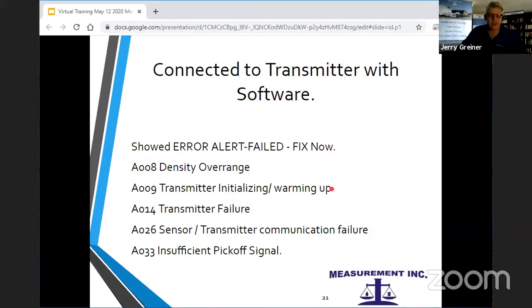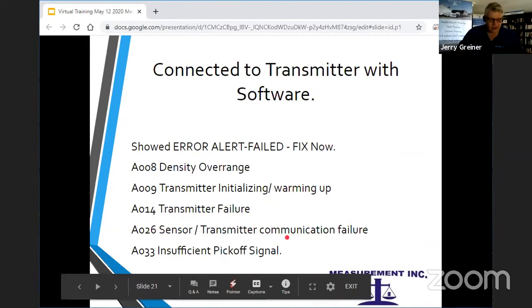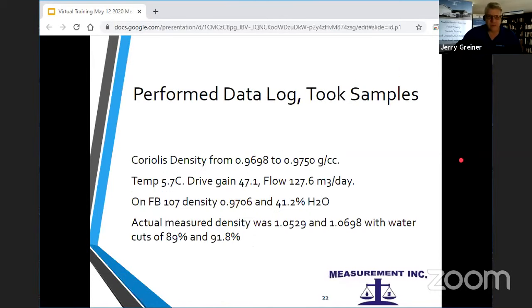Transmitter warming up or transmitter failure, you quite often get those from a power failure as well. Insufficient pickoff signal, sensor failure. There's some here. You don't usually see them all, but you do see them. So we performed a data log for a while. I thought, let's see what this thing is doing. So we wanted to see what is showing for density and what the real measured density is. And so we data logged it for quite a while.